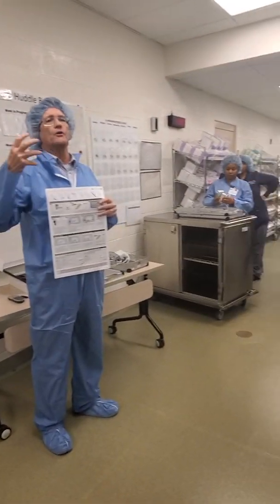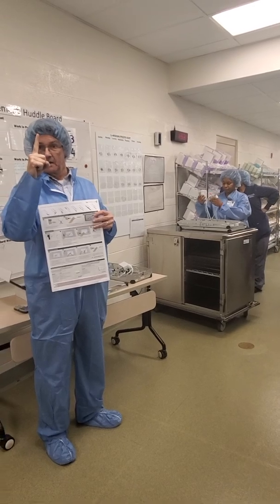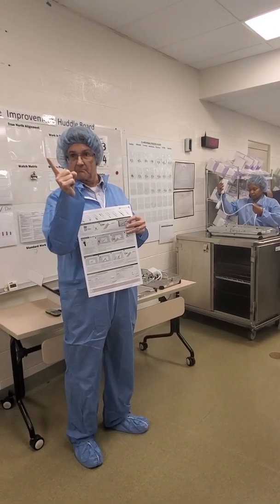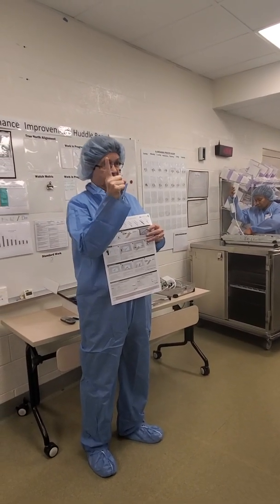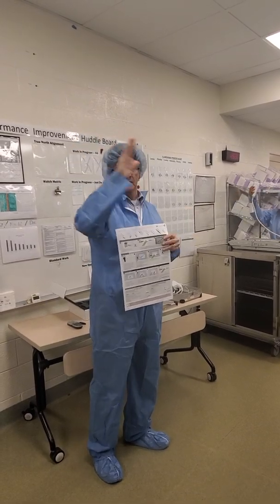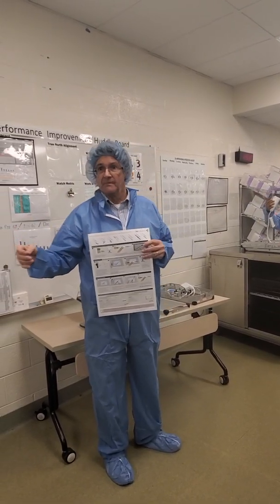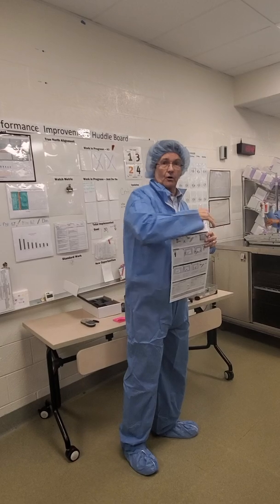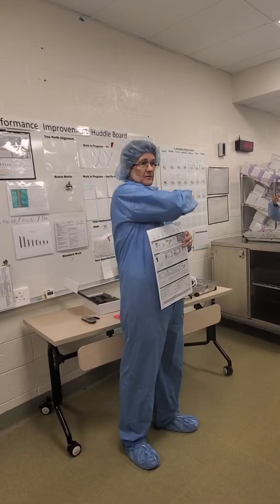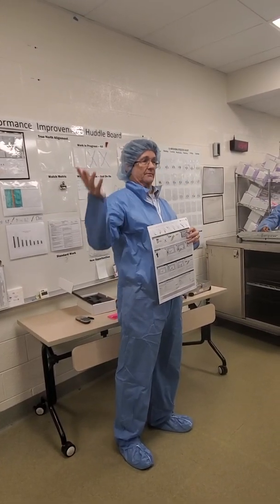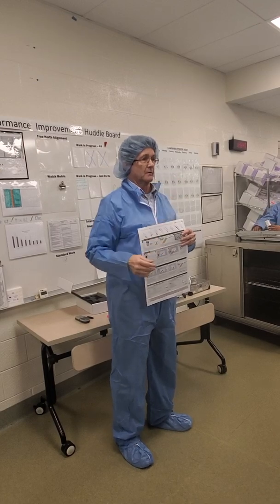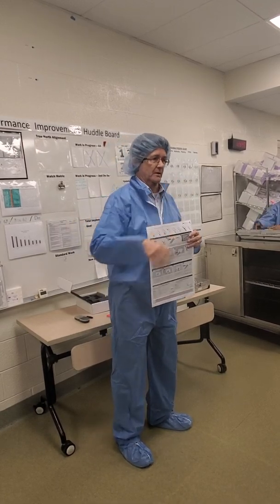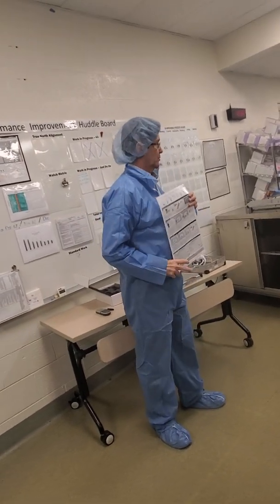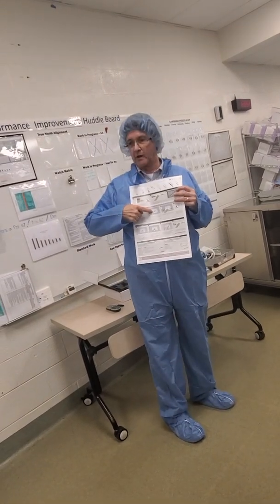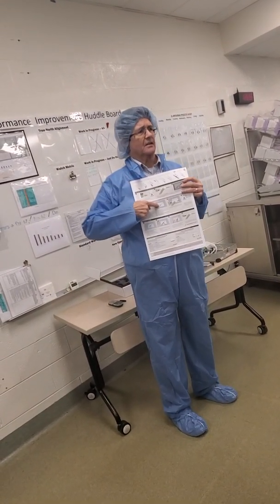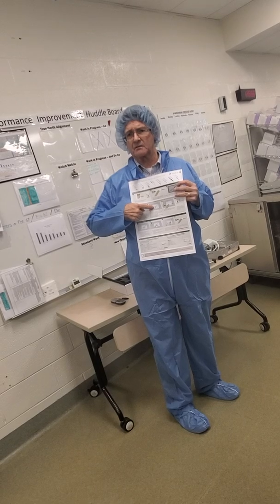Right, so all you're doing is you're making sure that needle doesn't do this. Okay? Because if it does that, you put it aside, you red tag it, whatever you do, and you say somebody's got to call BK Service to fix the probe, and we have to exchange it for a new one with money or whatever, you know, unless it's in warranty, of course. Anyway, so you put it in water, check for leaks. I think it's like 30 seconds, 40 seconds.